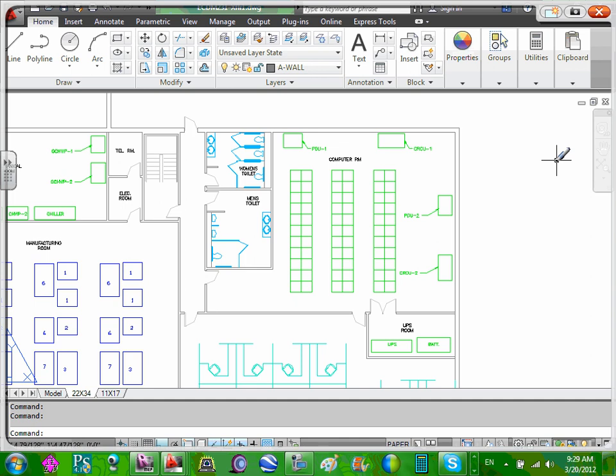There's really probably no line here in today's computer racks. Back when we started this, computer equipment was a little bit different, a little bit more like small washing machines that were back to back and lined up row after row. But what we're seeing today is a rack that's probably roughly 2 feet by 4 feet deep. And so we're looking at racks kind of facing each other. This may be the front side, the back side. I probably could do a different data center design, but we'll live with this. So if this is my front today, the rack, I don't know if you have been in a data center, we will get you a chance to get in one.